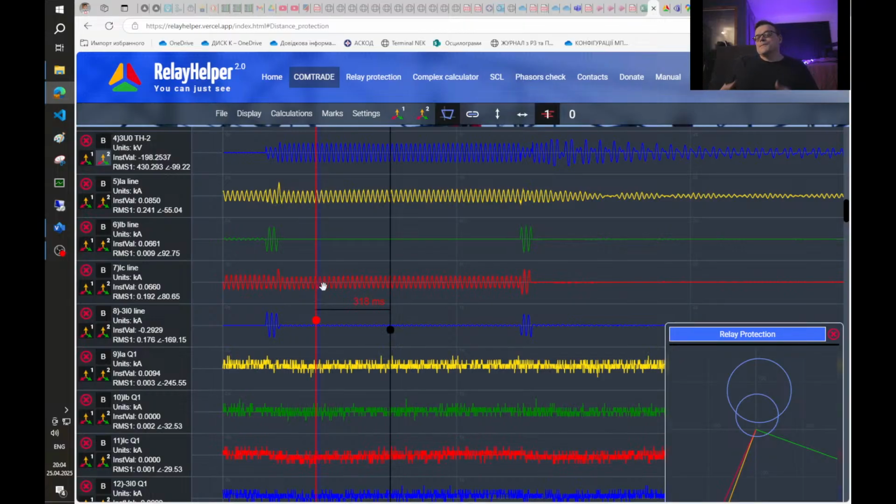Usually the second or third stage of the zero sequence neutral overcurrent protection is blocked during the single phase AR, and in this particular case the second stage of these protections was blocked, and also the third stage, but that part of it that worked with the teleprotection scheme.